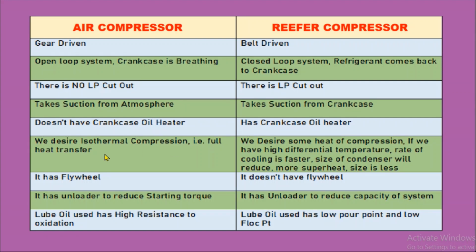Another important point is we desire isothermal compression in air compressor. That means we have the requirement of full heat transfer. Else in the reefer compressor we desire some heat of compression. So if we have high differential temperature and the rate of cooling is fast, then the size of the condenser will reduce and more superheat will happen and the size of the compressor will be reduced. This is why we require heat of compression in reefer compressors and we desire isothermal compression in air compressors.